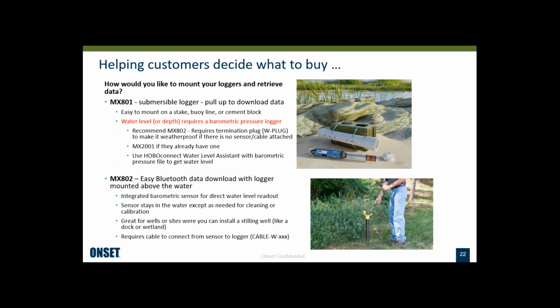It can be out of sight, so nobody knows it's there. And especially if there's like boat traffic, that's a good option. The one thing to keep in mind, though, with the MX801 logger is that they'll need barometric pressure to compensate for barometric pressure changes if they're using the CTD sensor. They only need this if they're doing depth measurements.